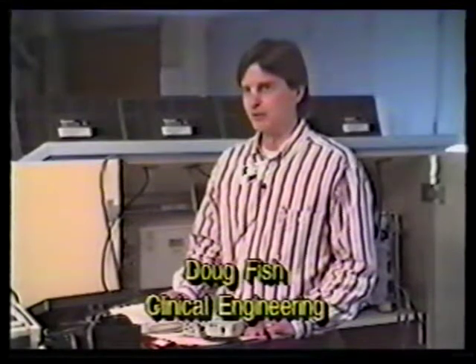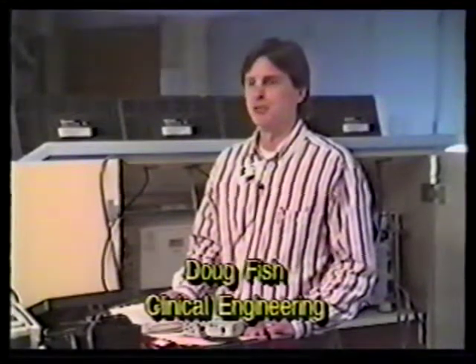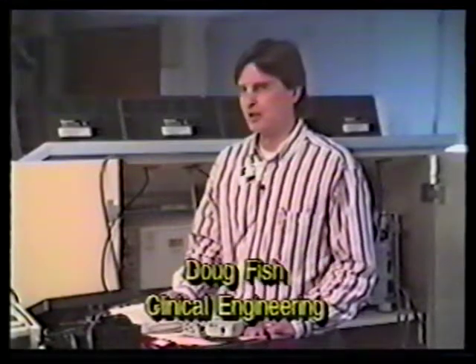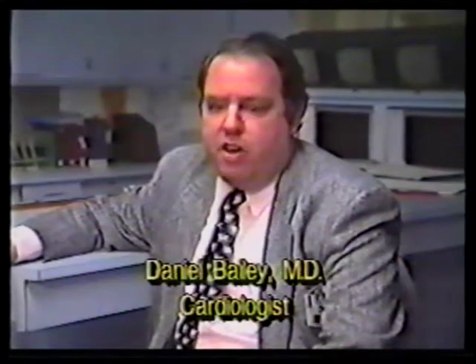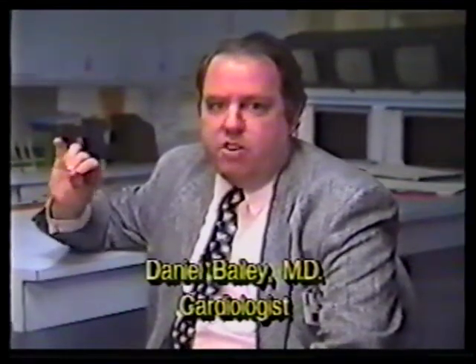Well, usually the human body has a fairly high resistance to the flow of current or electricity on the body, but if there's moisture on the body, or cuts or abrasions, or internal catheters or leads attached to the patient, it gives an entry point for electricity for a shock. The physiologic effects of electrical current exposure vary depending on the intensity, and the effects can vary from very minimal tingling in the fingers from a small current up to electrical burns or even cardiac arrest.